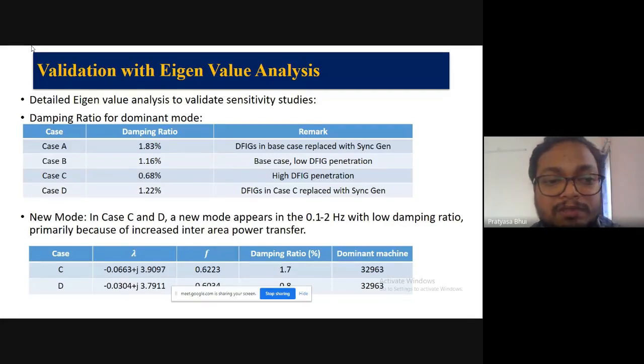However, we found that there was one more critical mode in cases C and D that was not present in cases A and B. The reason was that in cases C and D we have high DFIG generation, and that means it will change the power flow directions. So it is associated with increased inter-area power transfer. Basically, in one tie line, there was a huge amount of power transfer. Because of that, there was a new critical mode which was not present in cases A and B.